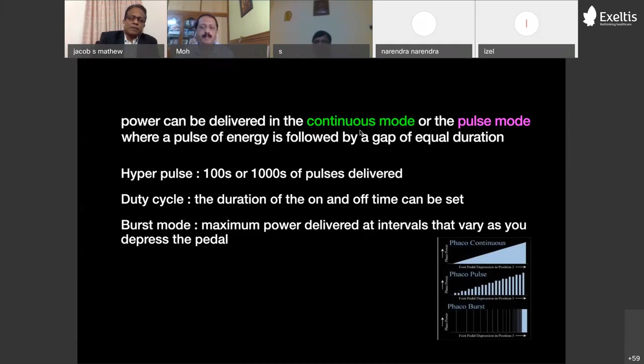So basically, fluid balance is the key to a successful phaco surgery. It's a closed anterior chamber, and for that you need a balance of the water that comes in and the water that goes out. It's not only the fluid that gets aspirated; some fluid leaks out through the side ports that you make. Also, some fluid might come out through the sleeve outside the tip of the phaco probe. That helps in cooling the wound. So this has to be balanced with the fluid that comes in. Usually the infusion is passive inflow, as I mentioned, with the bottle kept above the head end of the patient.